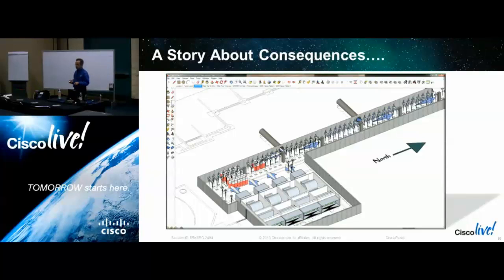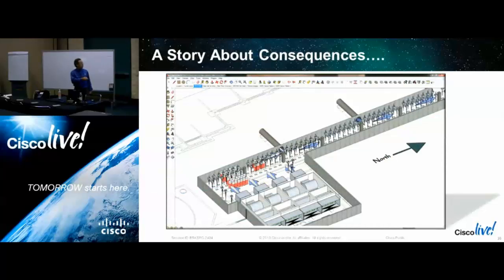There were some areas of the air tunnel that were unsealed concrete. And if you've ever been in the basement of a house on a fall or winter day and tried to heat and regulate the humidity down there, you know what kind of problems they were facing with that. They have 2 air tunnels. This is on the south side, and that's on the north. When we looked at the south side, it was heavily encrusted with this white powder deposit, and the north one really wasn't. A lot of other things were going on.